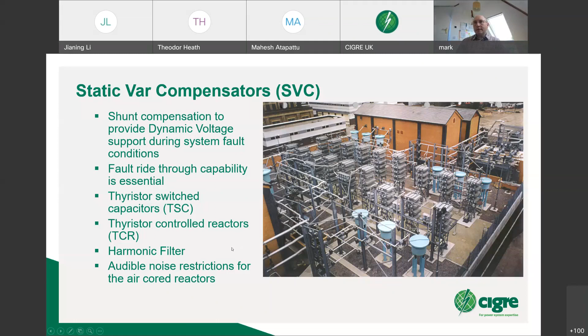So, moving on from an SVC, essentially the flavor or the favorite technology at the minute for dynamic shunt compensation is the static synchronous compensator, or STATCOM for short. This uses the latest generation of inverter based on voltage source converters, and is typically made up of IGBT modules. The big difference between this and the SVC is that a STATCOM can do both the positive and negative injection, so you don't necessarily need a capacitor bank or a reactor bank.